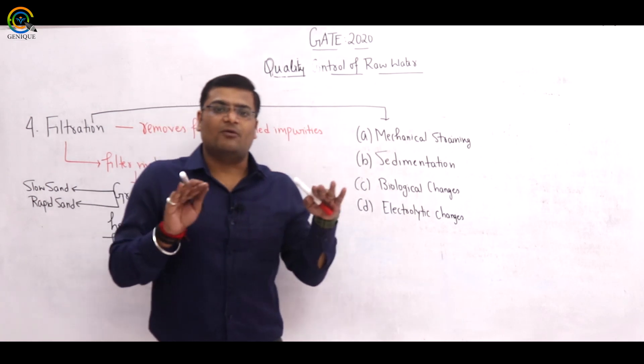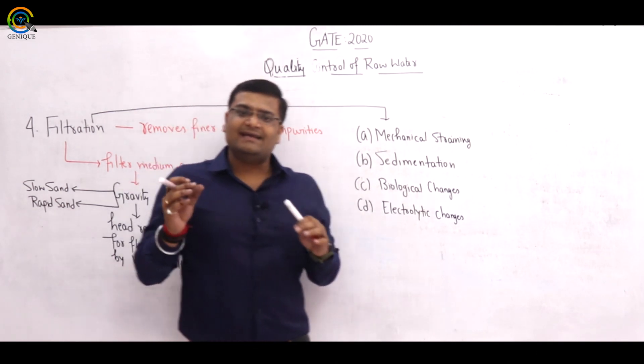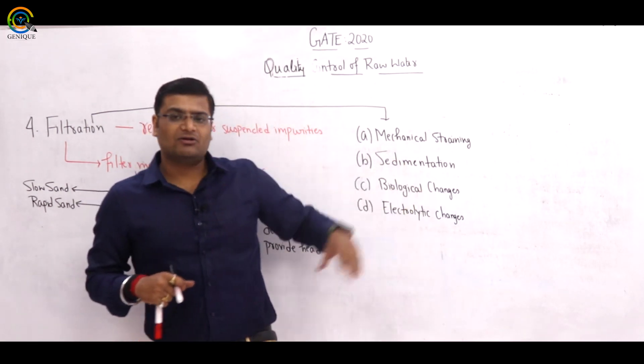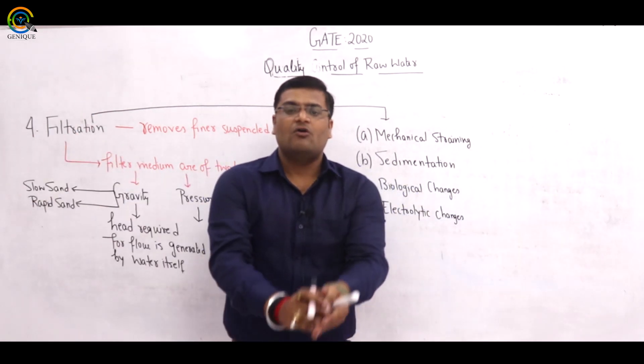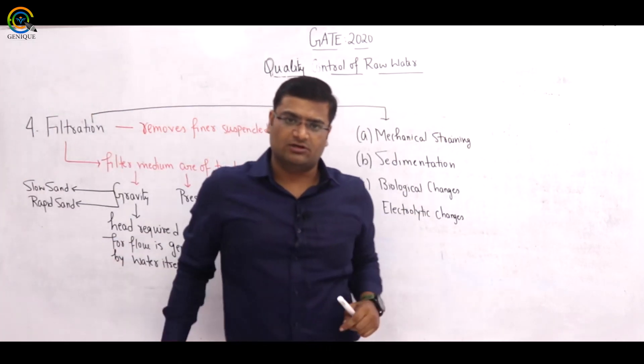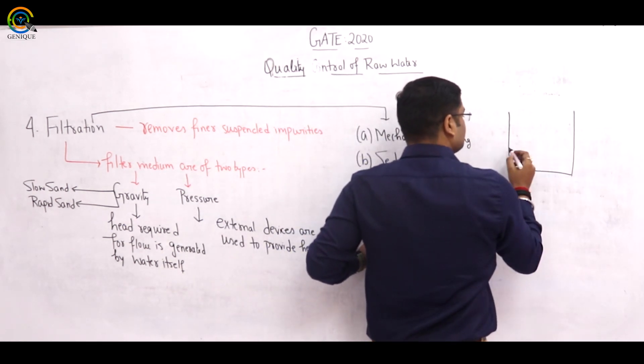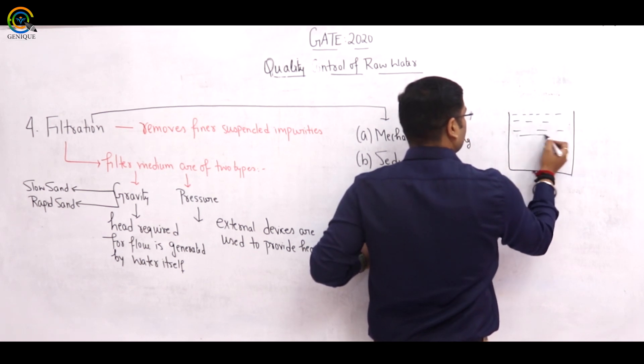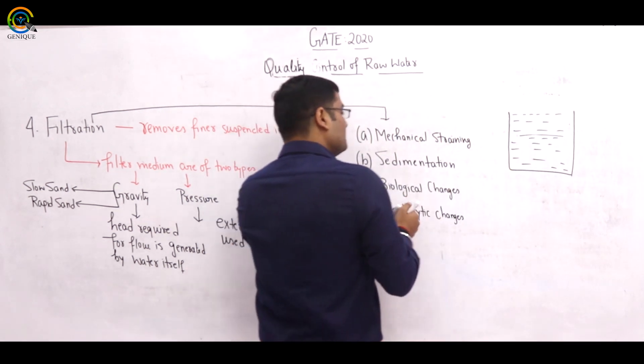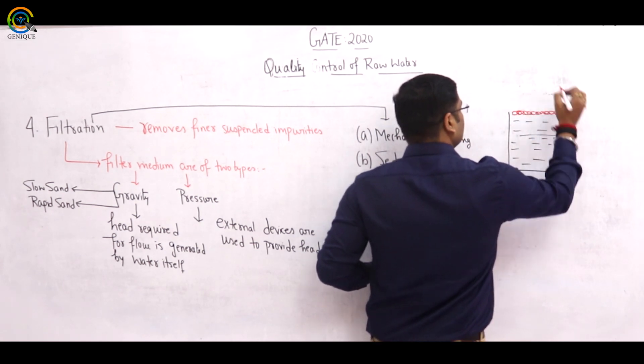In mechanical straining, the particles — the impurities — encounter the filter medium. The size of the void in the filter medium is smaller than the size of the particles. So the particles get retained because they are larger than the voids. This is the mechanical straining process. A top layer forms on the filter medium, and this is the sedimentation process at the top layer.